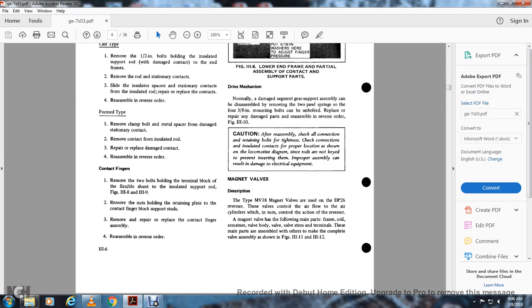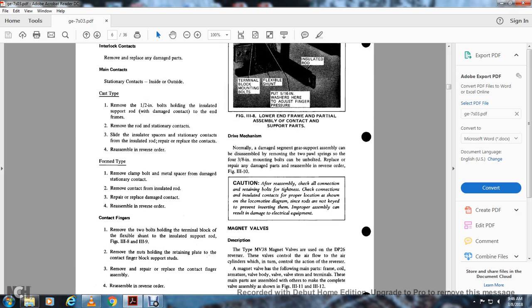Form type: remove the clamp bolt with the metal spacer from the damaged stationary contact. Remove the contact from the insulated rod. Repair or replace the damaged contact. 4. Reassemble in reverse order. Contact finger: remove the 2 bolts holding the terminal block with the flexible shunt to the insulated support rod. Figures III-8 and III-9. Remove the nut holding the retaining plate with the contact finger bolt block support studs. Repair or replace the contact finger assembly. 4. Reassemble in reverse order.